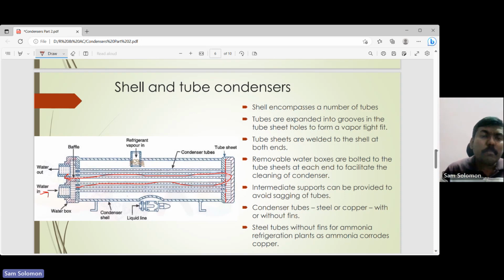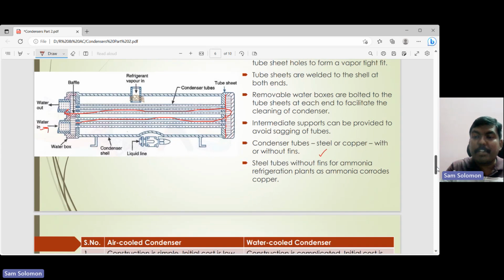Condenser tubes, once again, can be either steel or copper, and you can either have fins or no fins, whichever is convenient with your budget and with the requirement that is specified. All these parameters come into play. And in case of ammonia, we have already seen that the copper tubes get corroded when ammonia is used as a refrigerant in the ammonia refrigeration system. And so people normally use steel tubes, and that too without fins. So that is how shell and tube condensers are used in case of ammonia refrigeration systems.